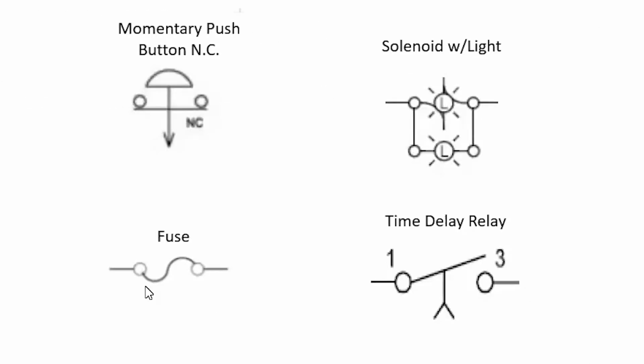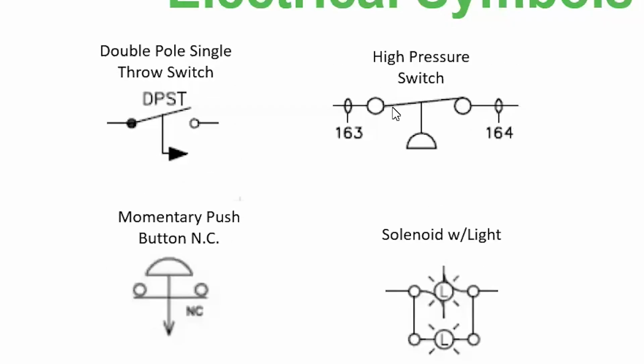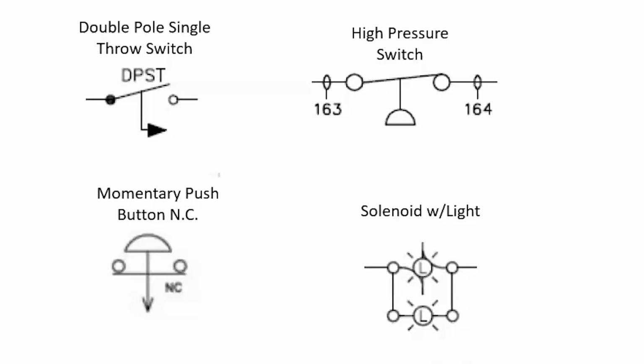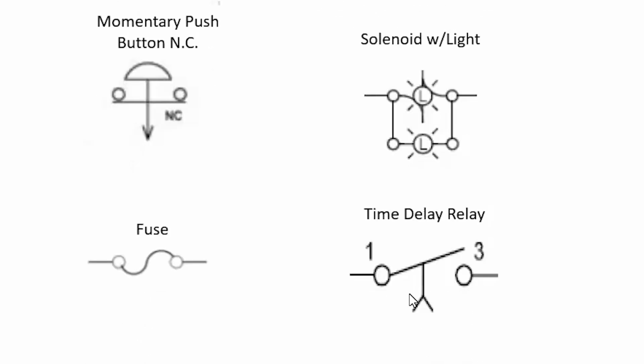A simple fuse is a straight line. I have a high pressure switch - if I don't know whether it's open on rise or closed on rise, how am I going to troubleshoot the system? I have a time delay shown by this little diagonal line here. I'm going to look on the drawing - how long has it been time delayed? Is it 50 seconds, is it 2 minutes? What is the time delay?